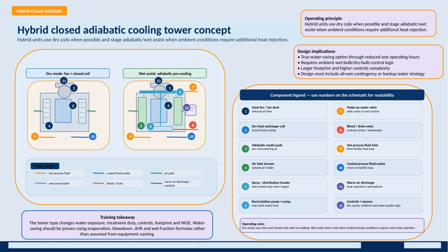Looking at the schematic components, the axial fan induces airflow, while the dry heat exchanger coil handles closed fluid cooling. The air inlet louvers allow outside air intake, and the adiabatic media pads pre-cool the air when sprayed by the distribution header. The wet assist water loop includes a recirculation pump, makeup water valve, and bleed valve to manage water cycles and prevent wastewater buildup.